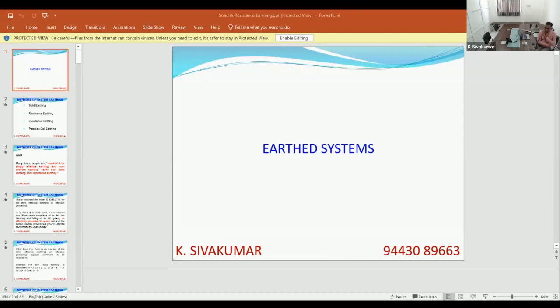I remember way back in 1993-94, I was working in Visakhapatnam. We did earthing for an industry very close to the coast. In those days, this much awareness was not there. They told us to put a pipe earthing, so we put a GI pipe earthing. After 1 year, we went and pulled the pipe. Only 1 foot of pipe came out. The whole bottom portion was corroded because it was saline soil.